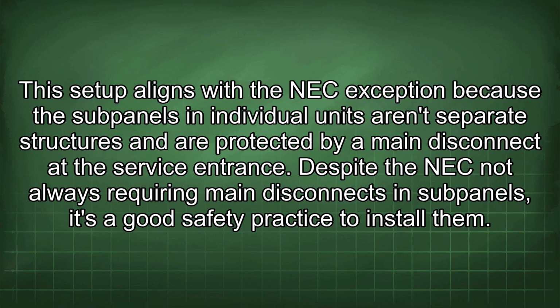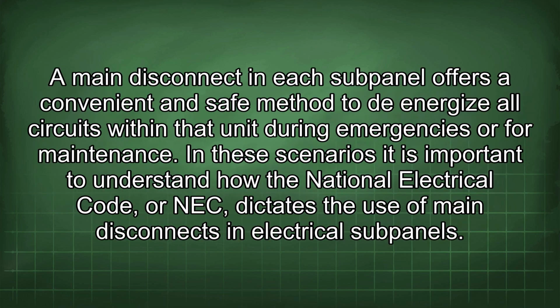Despite the NEC not always requiring main disconnects in subpanels, it's a good safety practice to install them. A main disconnect in each subpanel offers a convenient and safe method to de-energize all circuits within the unit during emergencies or for maintenance. In these scenarios, it is important to understand how the National Electrical Code, or NEC, dictates the use of main disconnects in electrical subpanels.